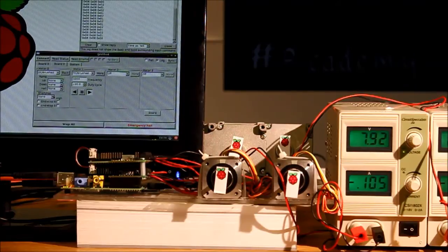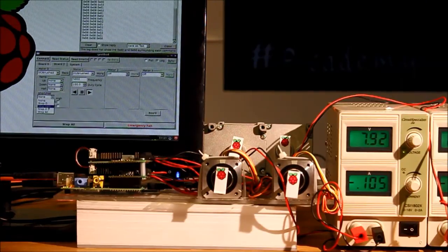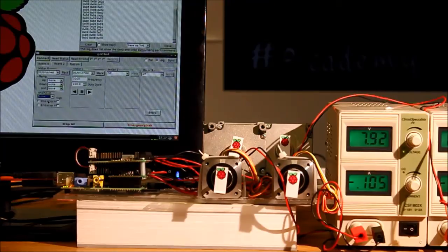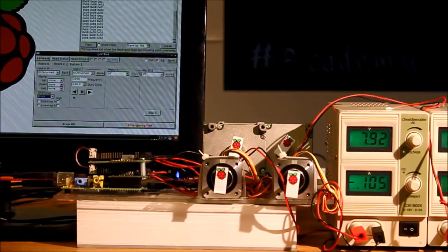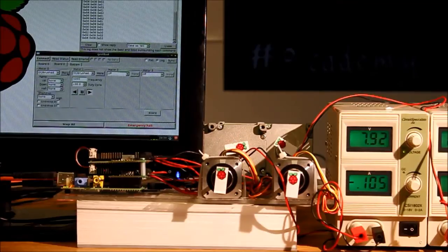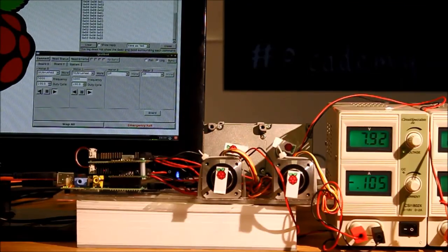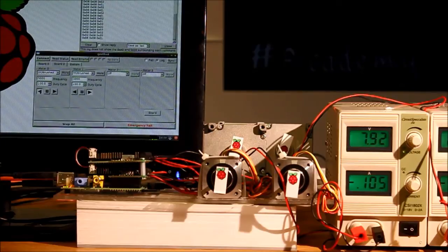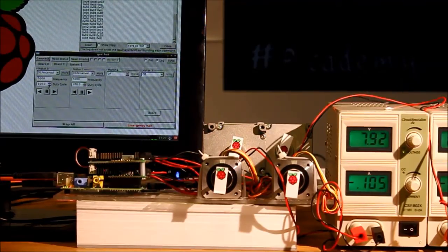However, I can do more modes. I can stop its own channel, I can also stop its adjacent channel, which I'm going to demonstrate now. We're going to start the second motor. I'm going to start this motor first. And now I'm going to set, if you see an error, stop motor 0 and 1. Going back, and I'm going to switch motor 0 to full reverse. And as you see, both motors stop.